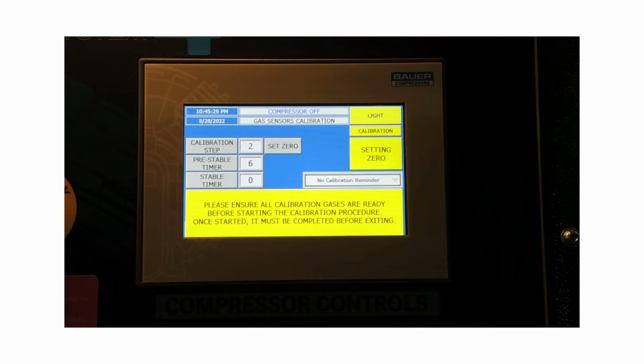We're going to be counting down the pre-stable timer on our 0 gas. Once it gets down to 0, then it'll go into the stable timer, and that's going to count down. Once it's at 0, then it'll be asking us to go through the span. So we'll want to get our 20 part per million gas ready. Now at this point I'm going to connect the 20 part gas.